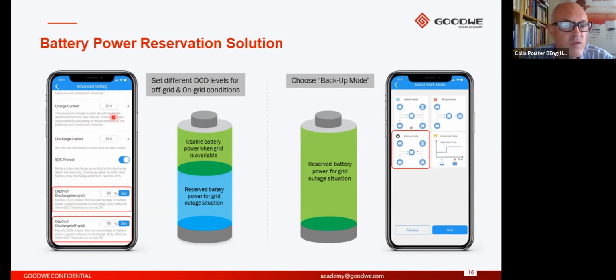So when we're looking at general mode, you may want to consider how the batteries behave in an intelligent way. You may be considering, well, what happens during a power outage, or in fact, do we suffer from any power outages? And if it's a frequent event that occurs, then you may want to consider reserving some power for the situation when you do lose the grid. If you don't set up this capability and just leave it as default, then when you are operating in general mode, the battery will be allowed to charge and discharge as it sees fit during the course of the day. Now, if you got to the end of the day and the battery had been depleted down to its set level of depth of discharge, and you happen to have a power outage, then you've got no reserve power left in the battery. So that may be something you need to consider.